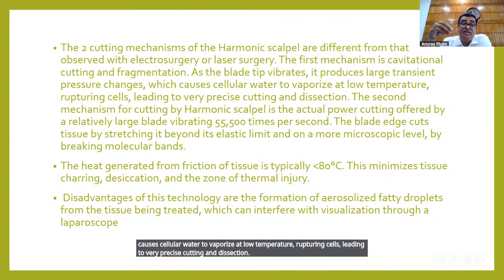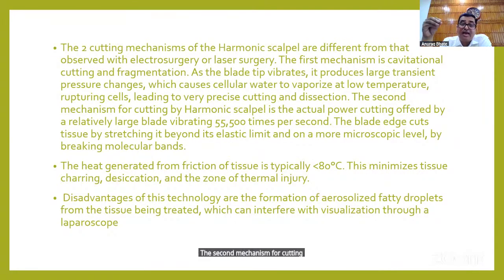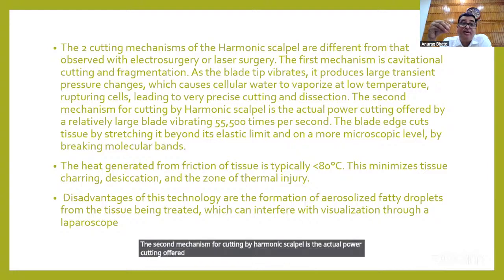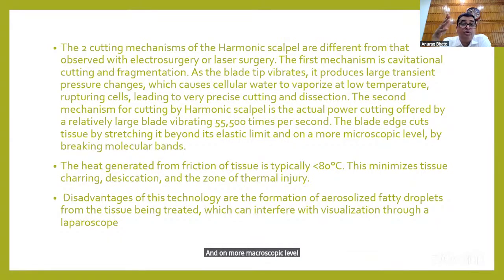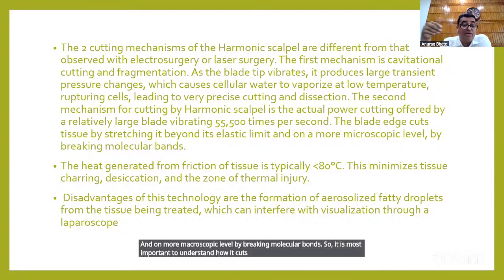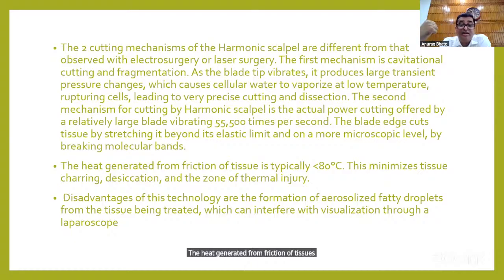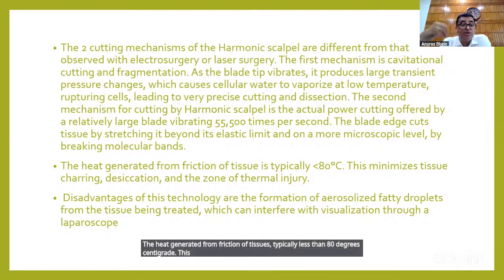The second mechanism for cutting by the harmonic scalpel is the actual power cutting offered by a relatively large blade, which is vibrating at 55,500 times per second. The blade edge cuts tissue by stretching it beyond its elastic limit and, on a more microscopic level, by breaking molecular bonds. So it is most important to understand how it cuts or coagulates the tissue. The heat generated from friction of tissue is typically less than 80 degrees centigrade. This minimizes tissue charring, desiccation, and zone of thermal injury.